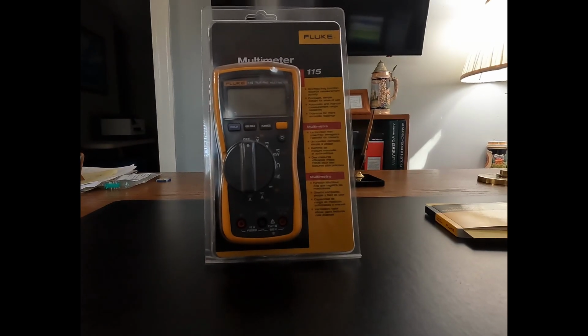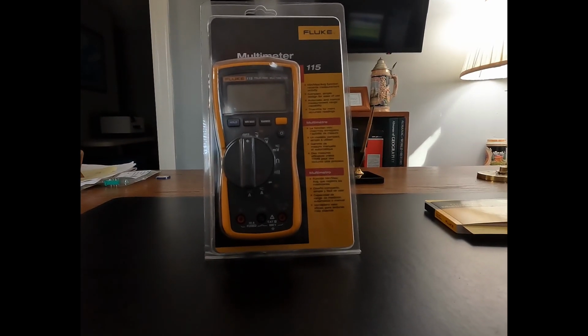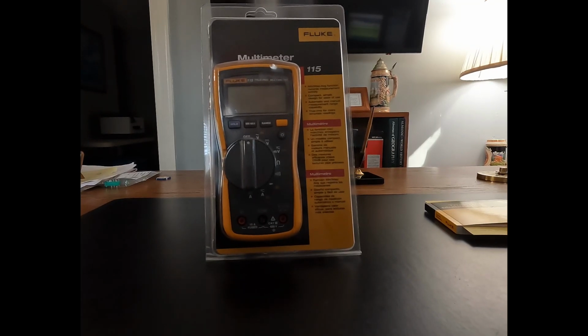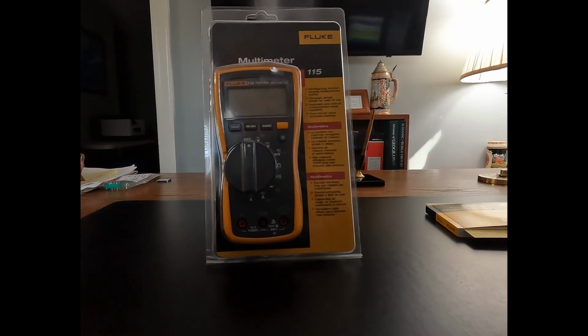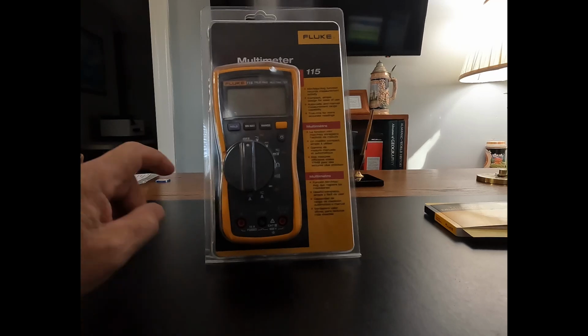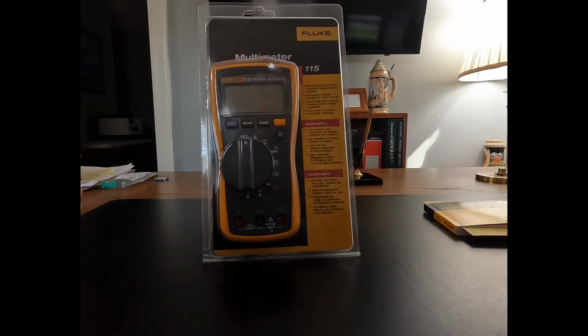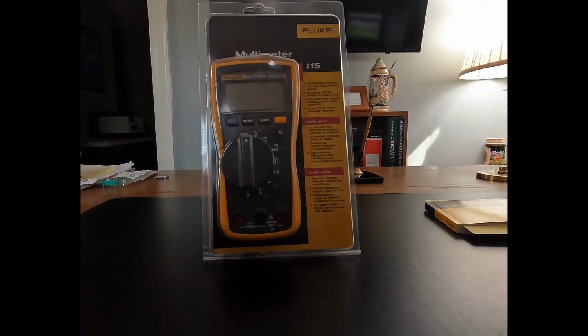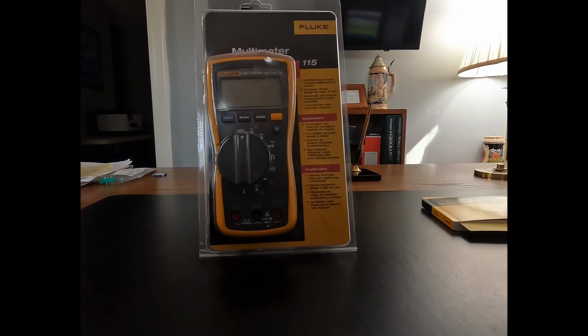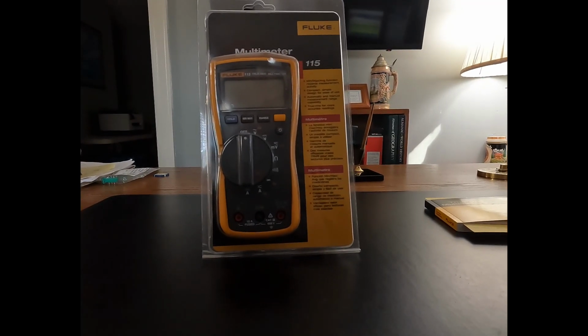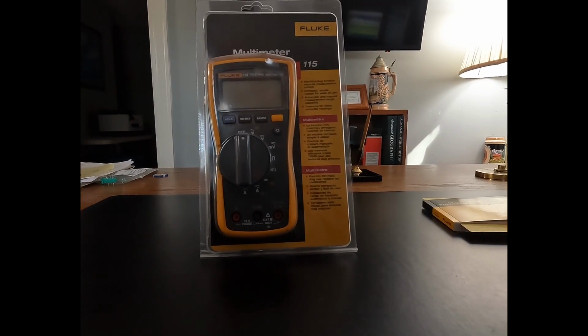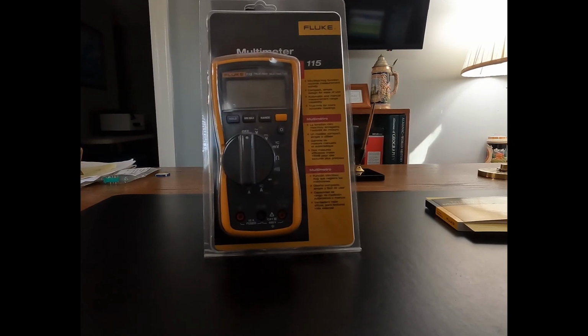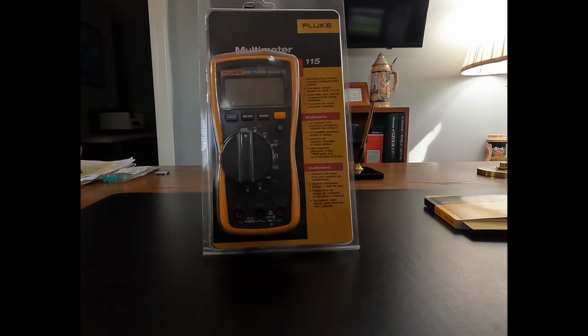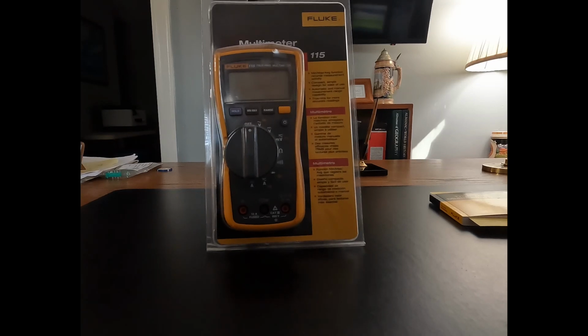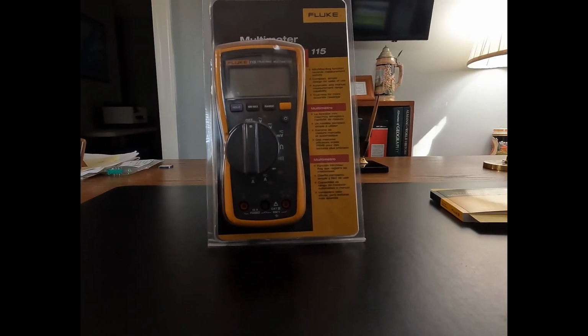That feature is called non-contact voltage, sometimes called volt alert. There's a function on that meter that allows you to select it, and anytime the meter gets in close proximity to a live AC signal, it will beep to let you know you may be getting close to something you should try to measure.